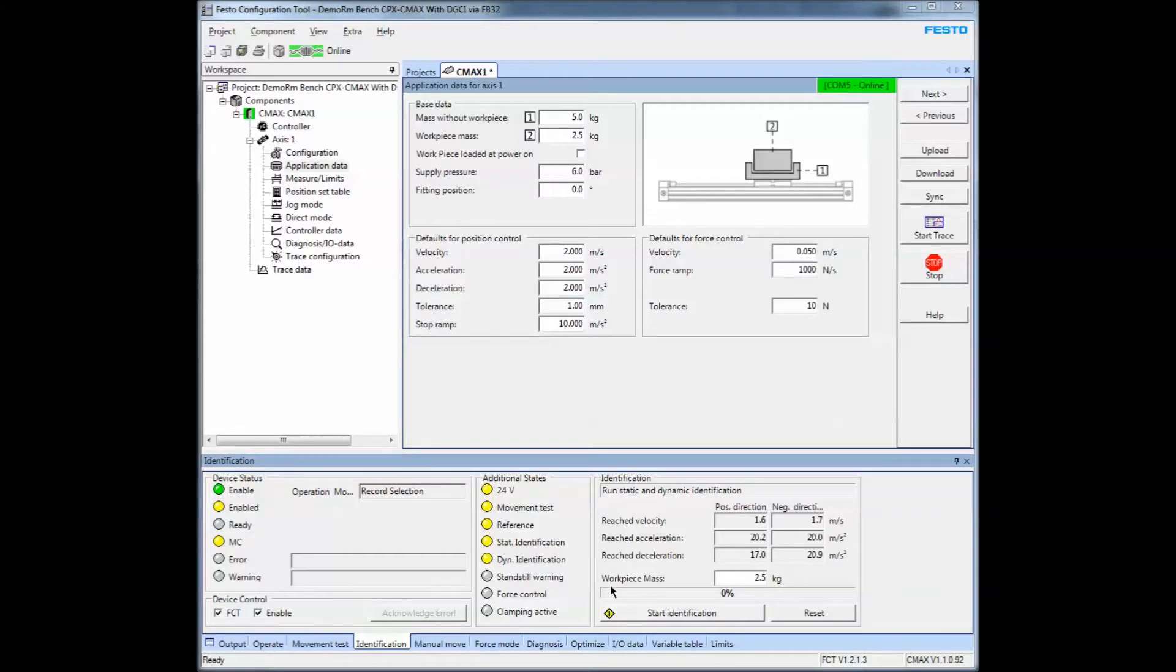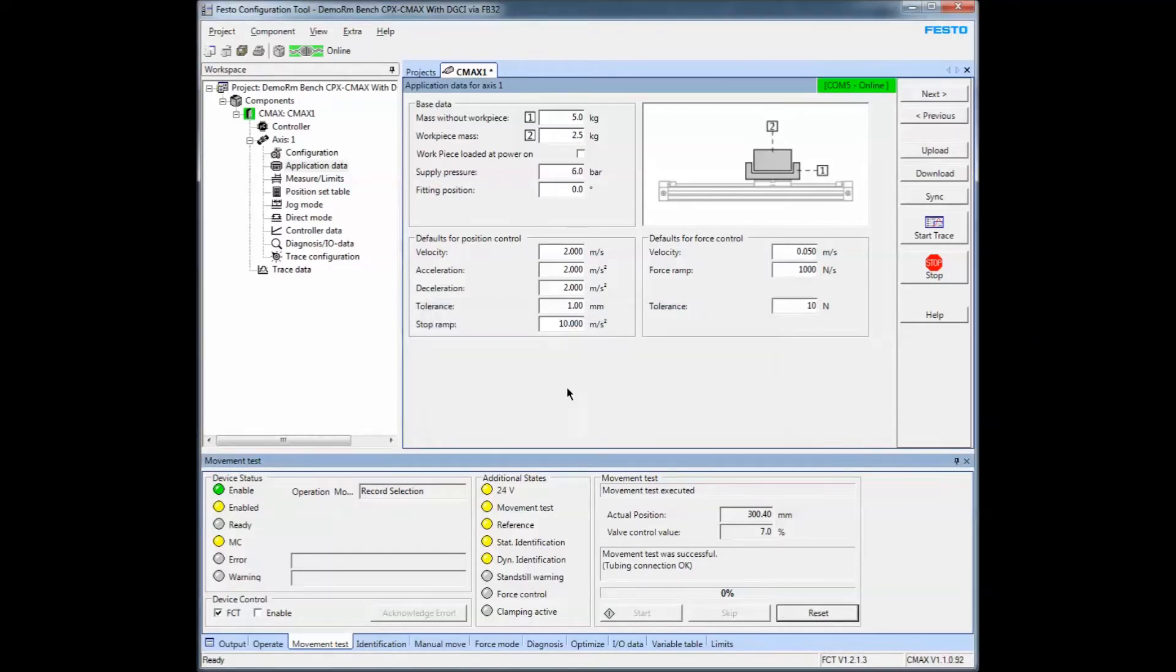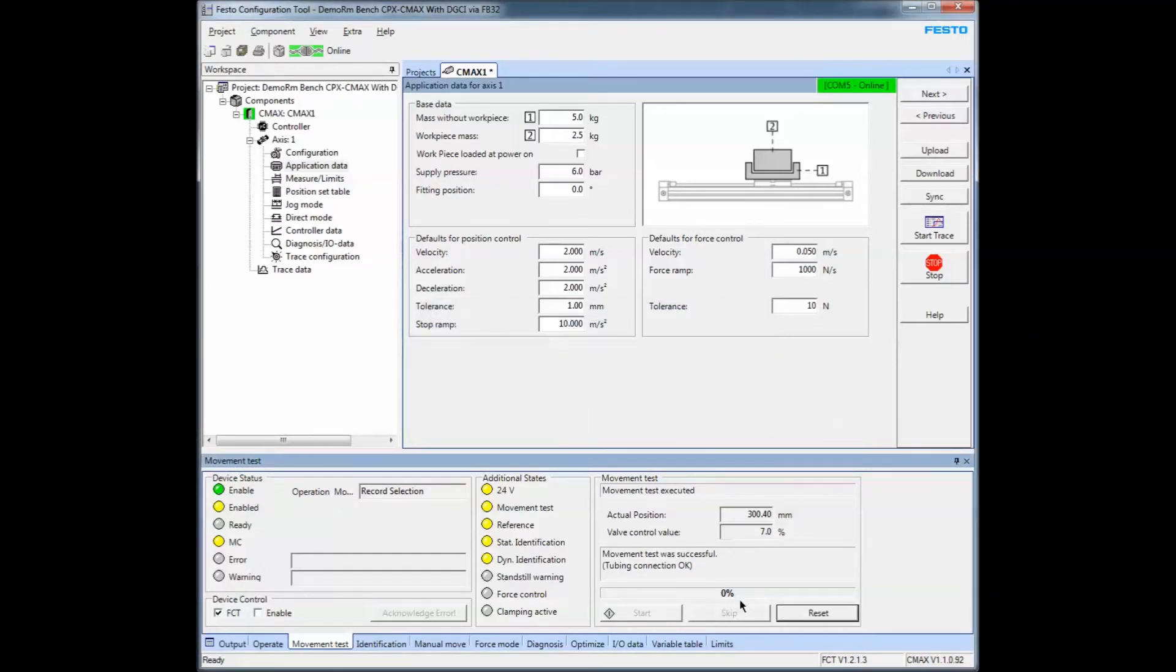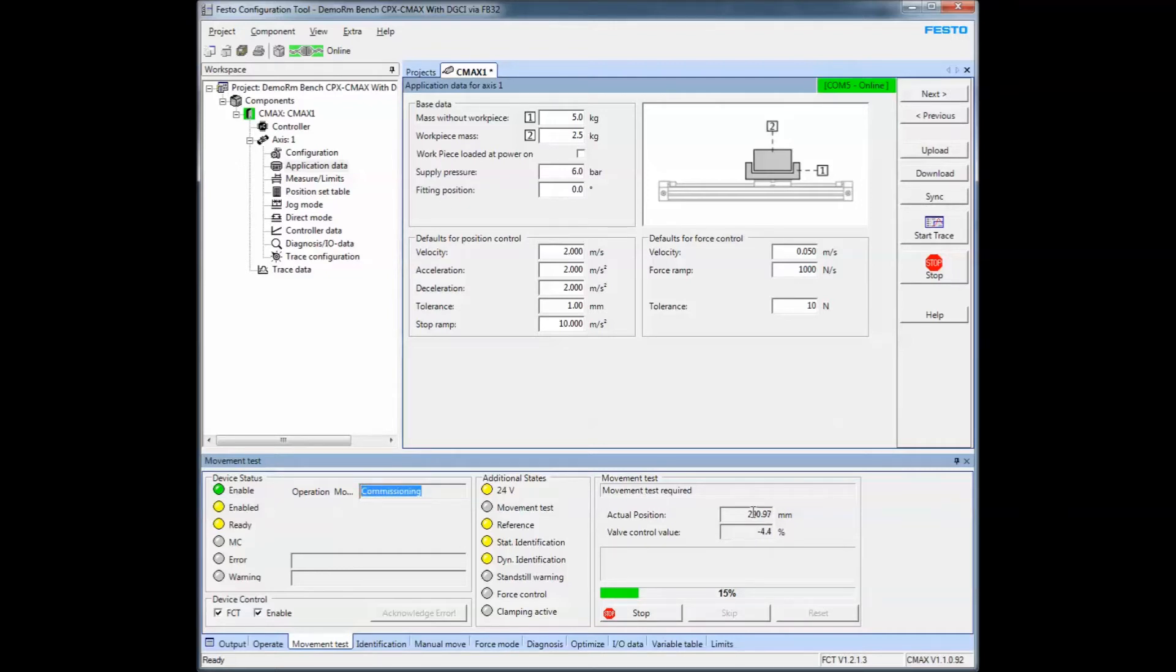Okay, so we're uploaded. Like I said, I've already done the test, but you can reset it, click on that, click start, and it will execute the test. It sets itself into commissioning mode and starts to move the axis back and forth. You can see by the value of the position that it's moving back and forth.